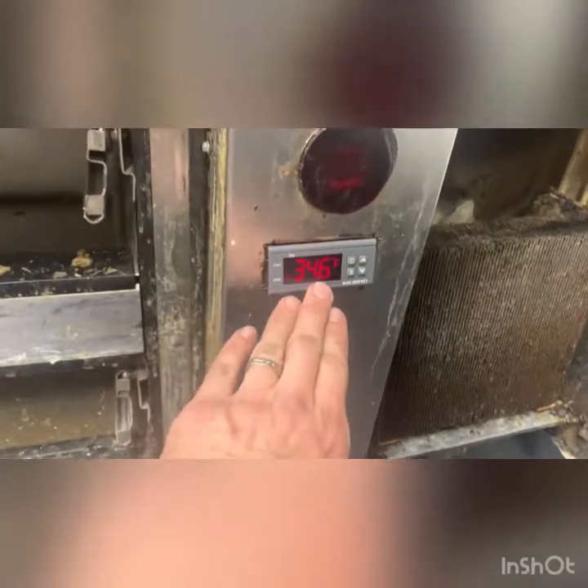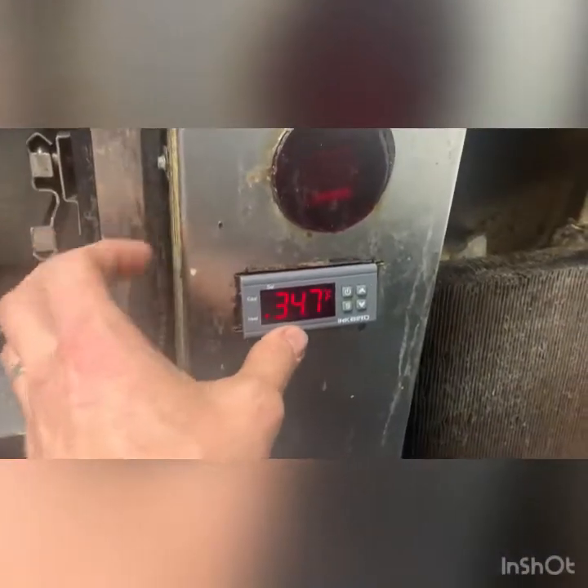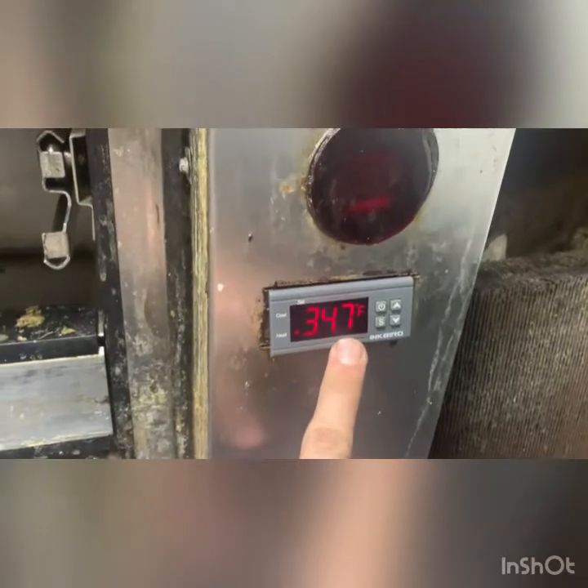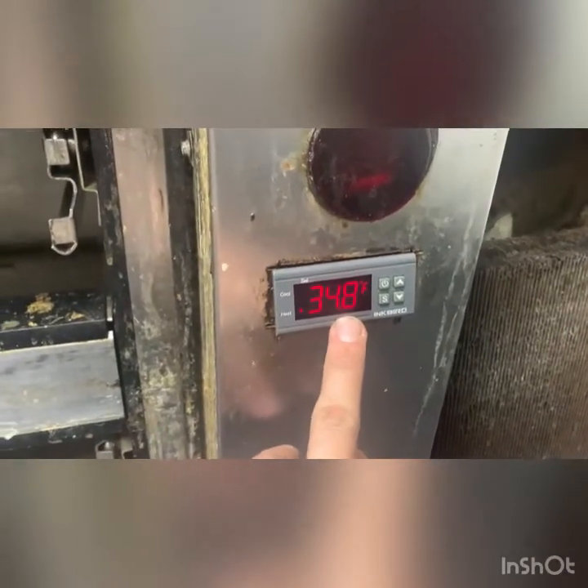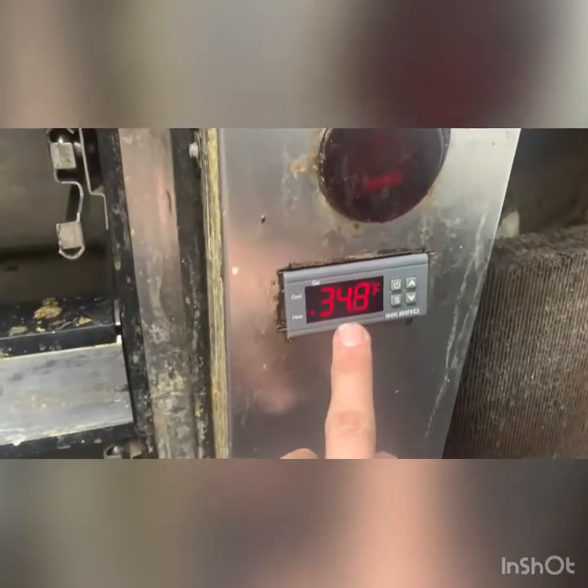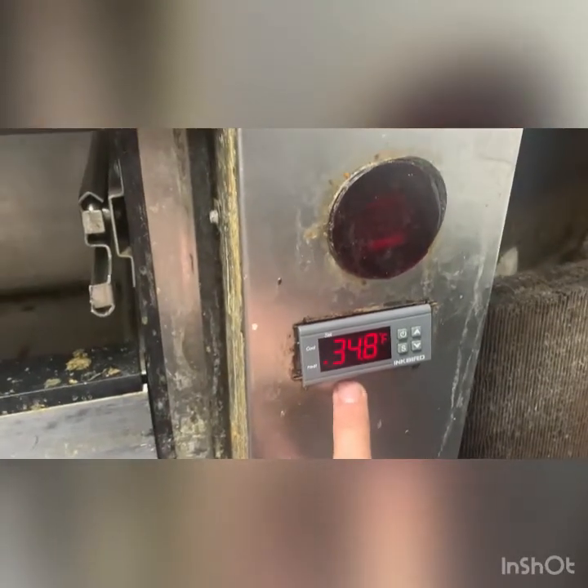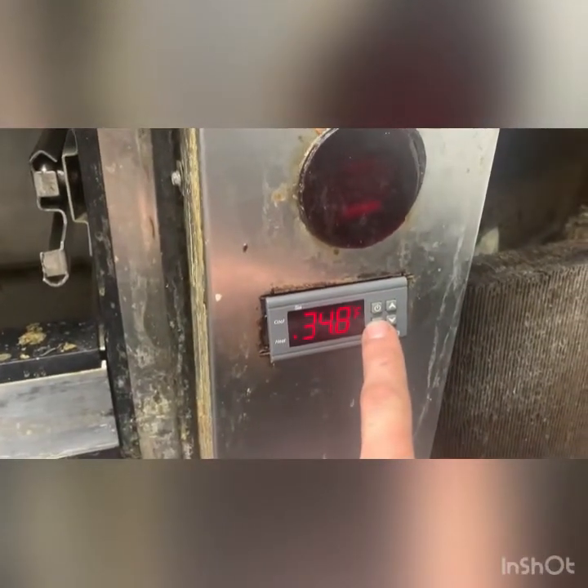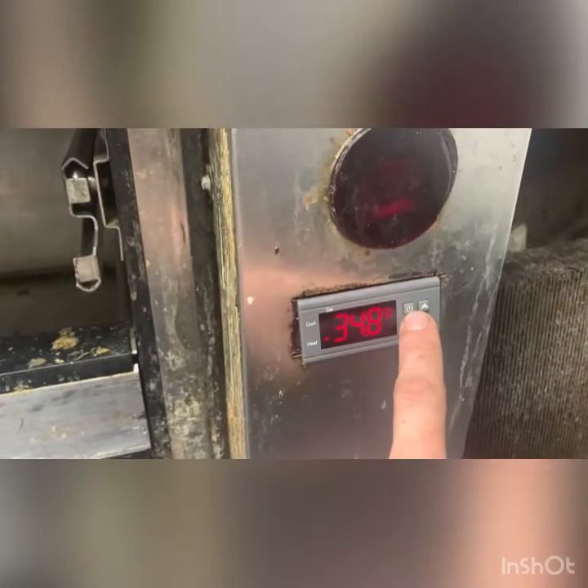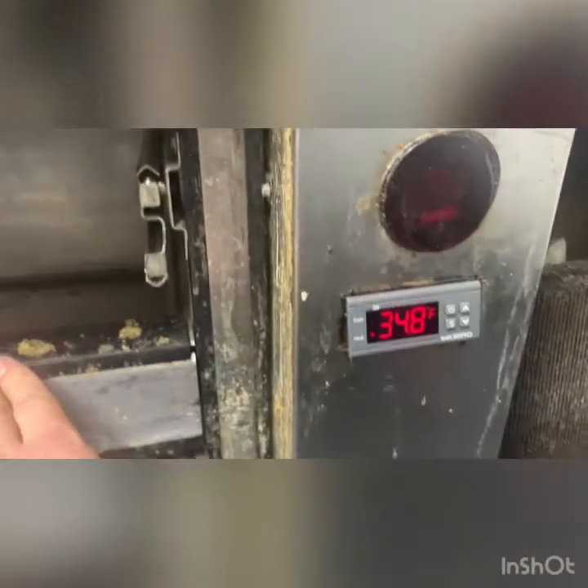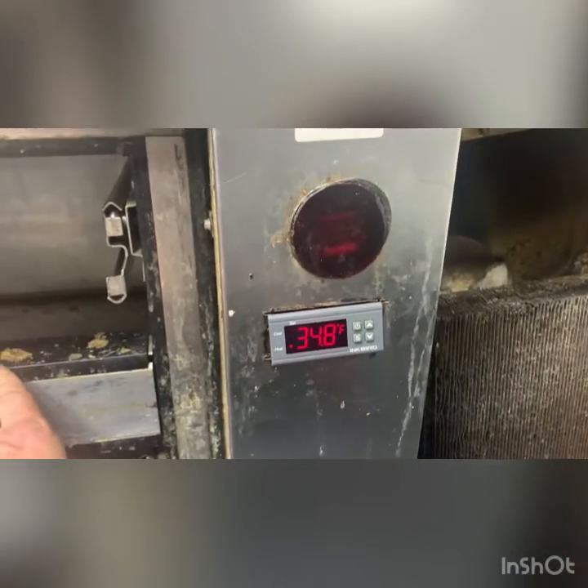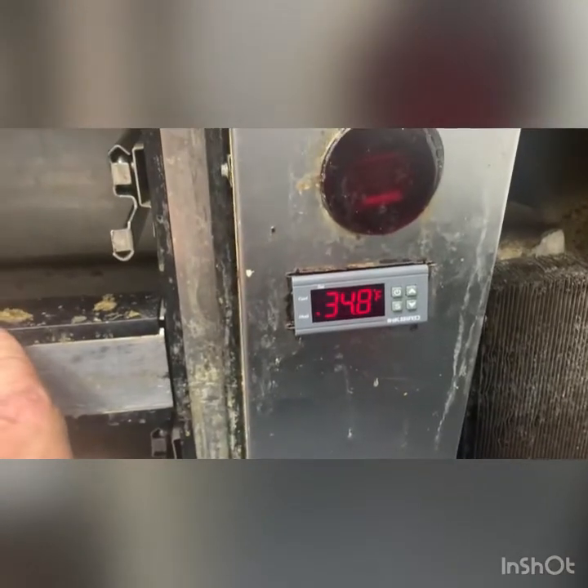Okay, so you can see we're climbing. As we pull the warm air into the evaporator, it melts the ice, and this is going to go up. So obviously at 32, the ice started to become liquid. I'm going to let this run all the way up to about 40 or 42 degrees, and then I'm going to adjust the set point and the differential, and I'll show you how we do that. Then we'll put the drawers back in, and we'll watch to see that it cools down and satisfies.